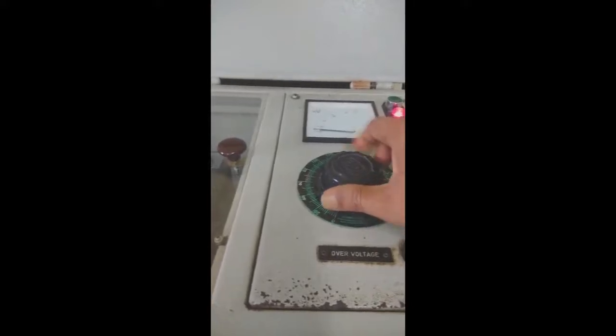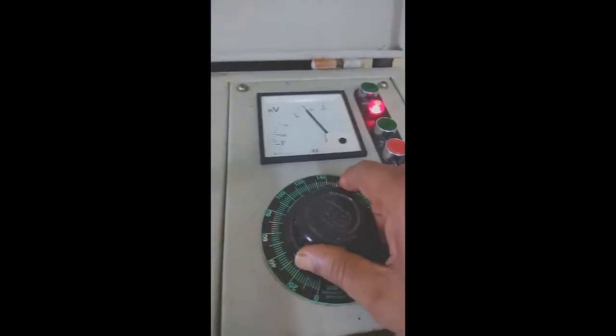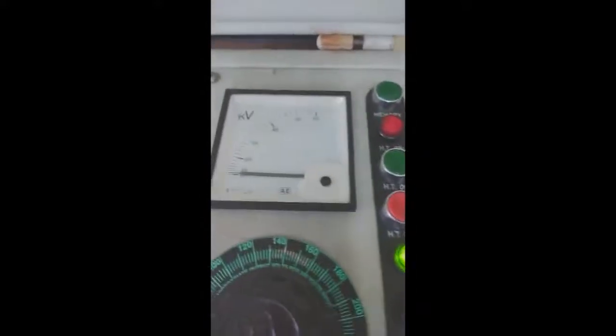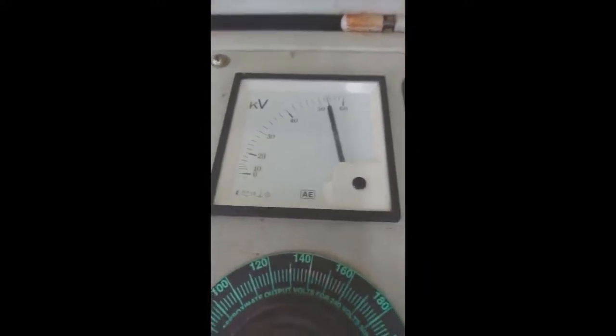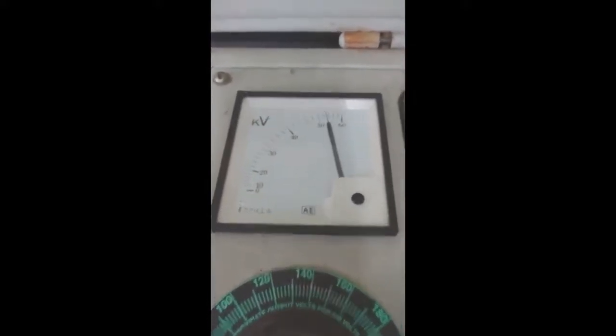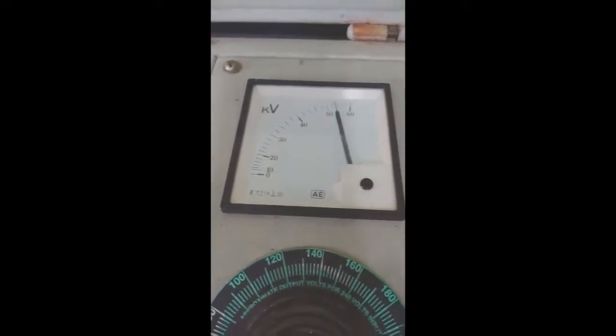Just gradually increase it at a rate of 2 kV per second. And for this voltage we will increase it up to 60 kV, and that has flashed, and the MCB has tripped. So by pressing this memory you can get the breakdown voltage of this insulating oil, that is 53 or 54 kilovolts.